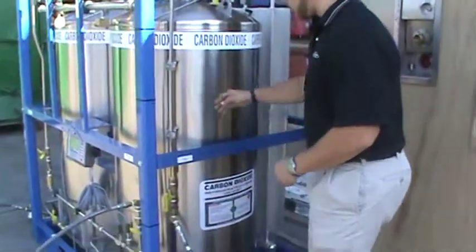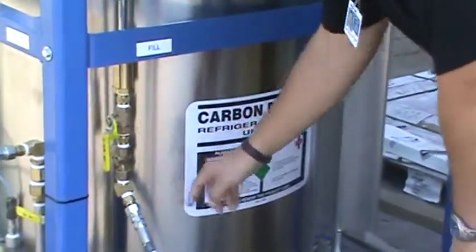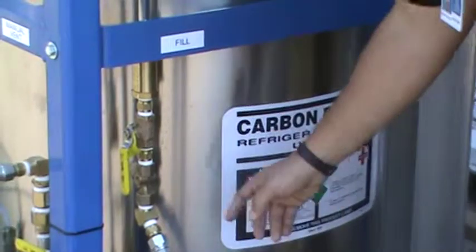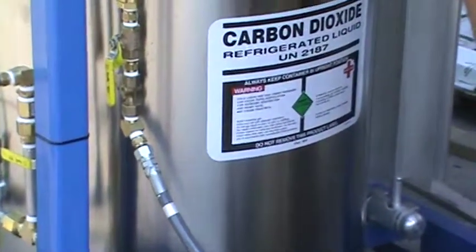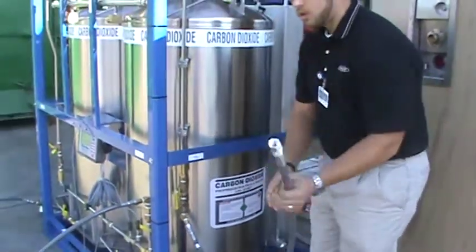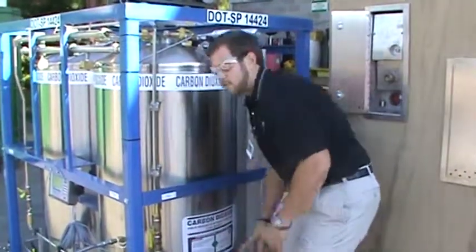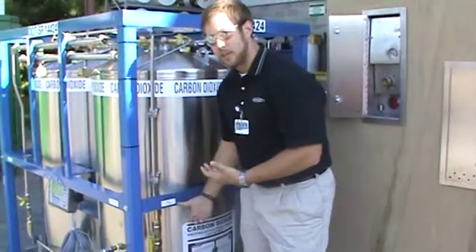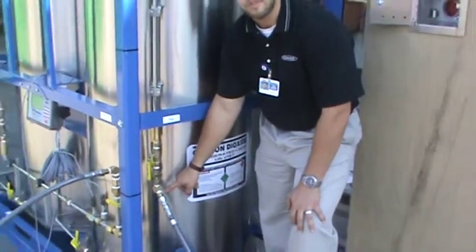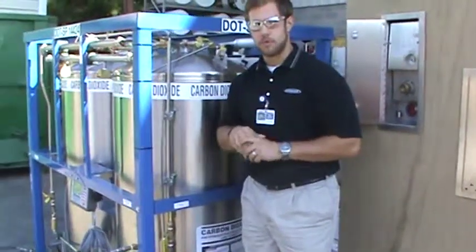This is our fill unit. We have a fill valve and your fill connection here. You also have a check valve in place so you can leave this fill valve open. We include a 5/8 flared fitting that goes with our transfer hoses. You can use this to fill the VLCD just fine. We give you the opportunity to change out the fitting if you so desire — we give you a female elbow here so that you can put whatever fitting you would like. We do ask, however, that you only fill through the fill circuit and through no other method.